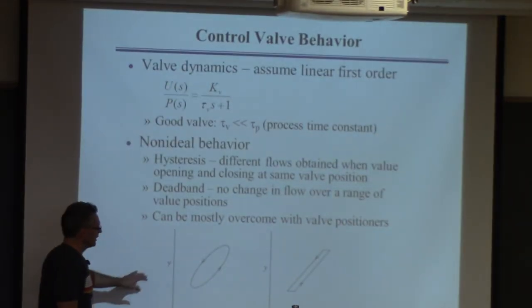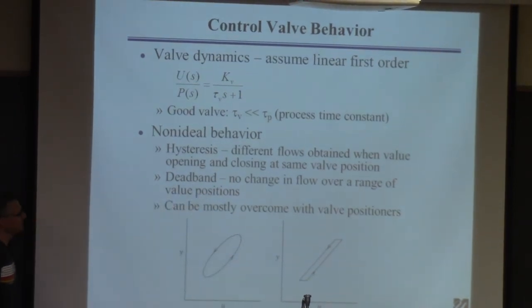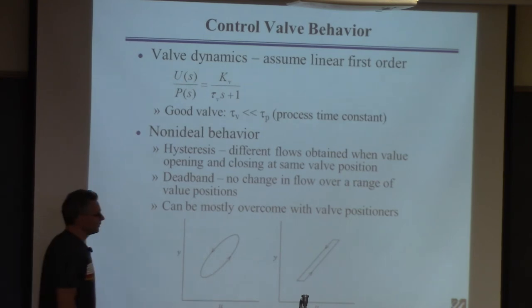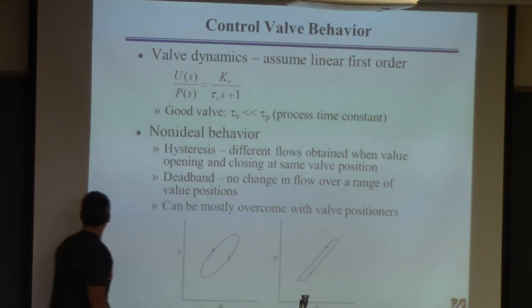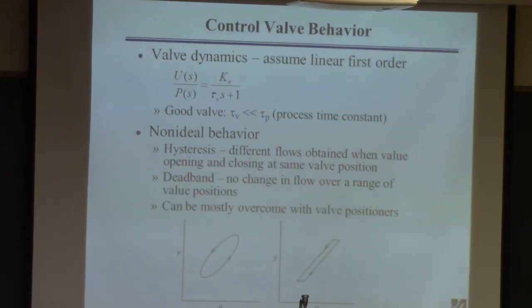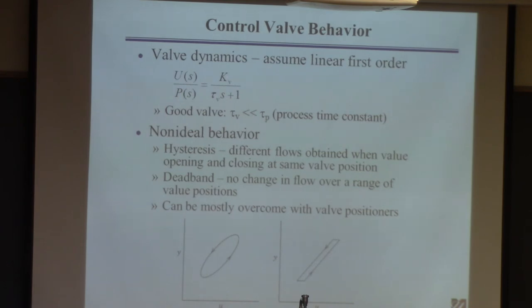There's something called a valve positioner you can put on the valve to try to overcome some of these problems. But if you are a process engineer or a control engineer, you will see all kinds of problems with these valves. Operators are constantly going out and trying to maintain and fix them, because your ability to operate the plant in an automated fashion depends intimately on these valves. Most modern control systems can monitor the position of the valve in addition to the flow coming out. If you start to see your valve exhibit this behavior, someone has to go into the field and fix it. In a typical plant there are hundreds of valves, and at any given time a subset of them aren't working.